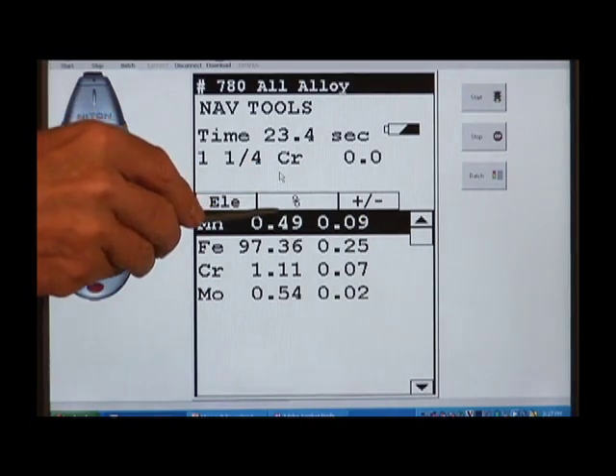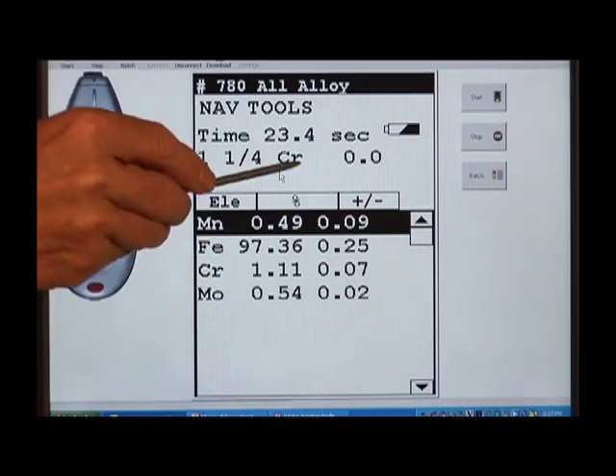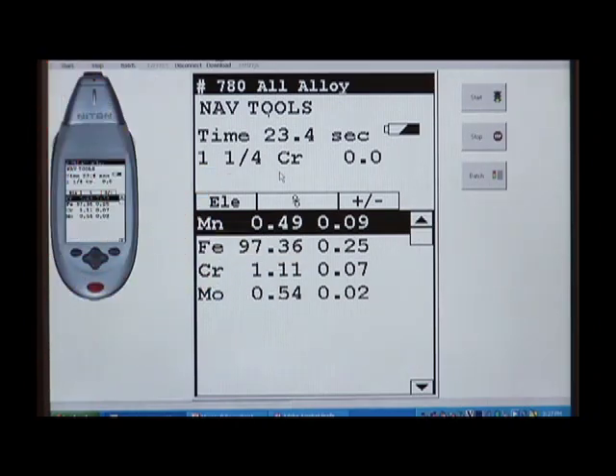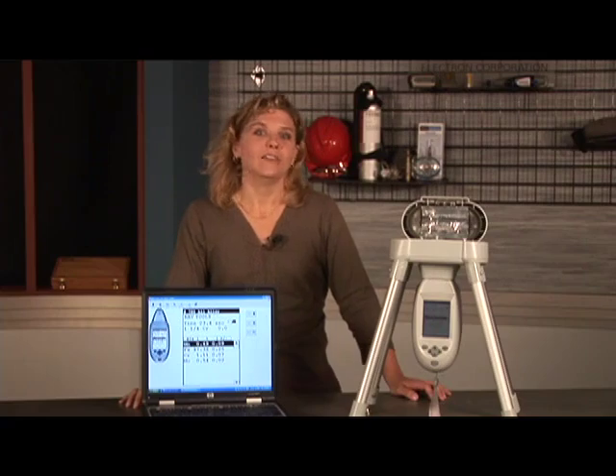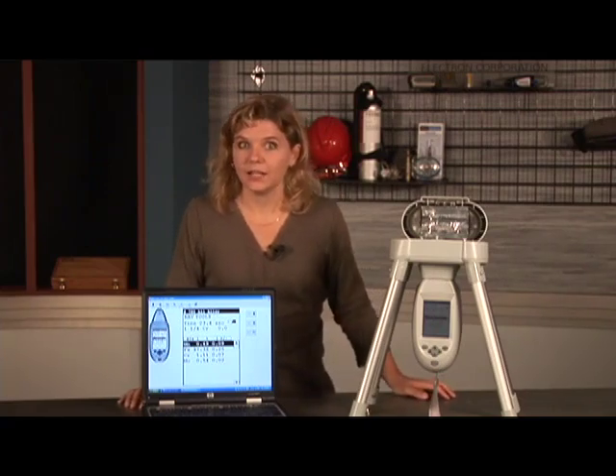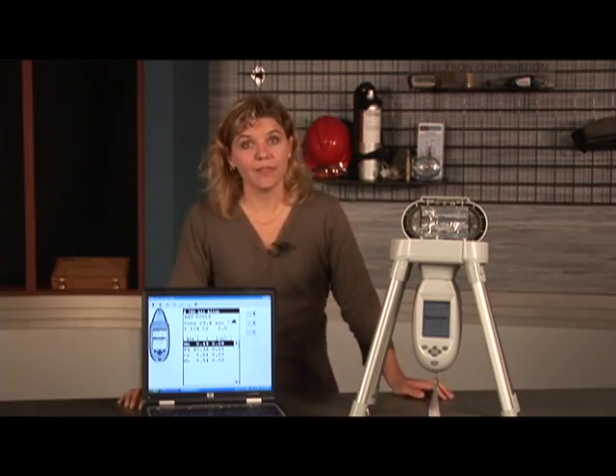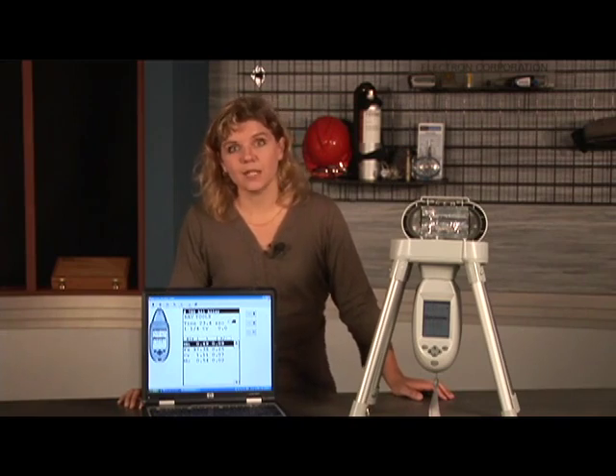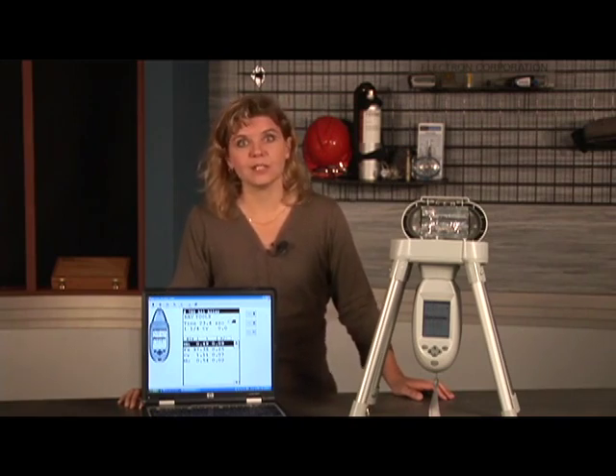The percentage readout in the center column, and the 2 sigma standard deviation, or the precision of the measurement, in the right-hand column. If your analyzer correctly identified 1 1/4 chrome half moly and the values of the major alloying elements are close to that of the certification data sheet, your analyzer is ready to go.